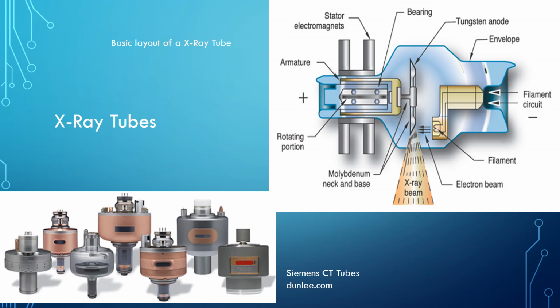In this example, the anode is made of tungsten. Those electrons will interact with it, and the anode in CT scanners, though it's not always made of tungsten, will rotate, and that helps to dissipate the heat, because this process generates a lot of heat. And then the X-rays are produced as these electrons interact with the anode, and it creates that X-ray beam.